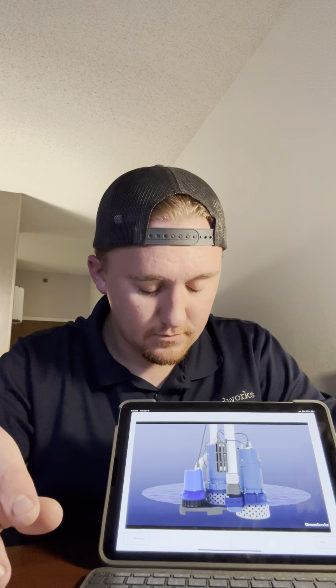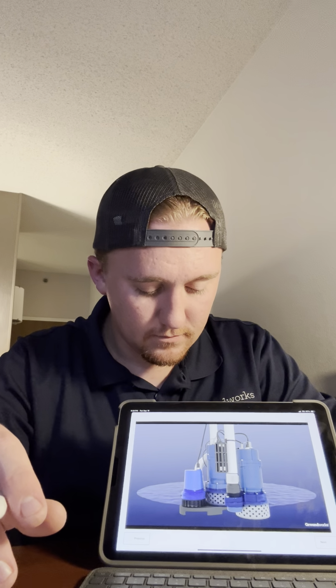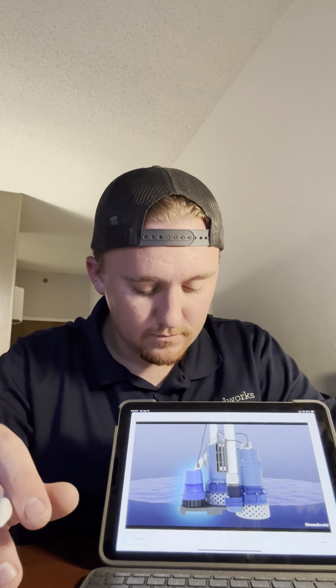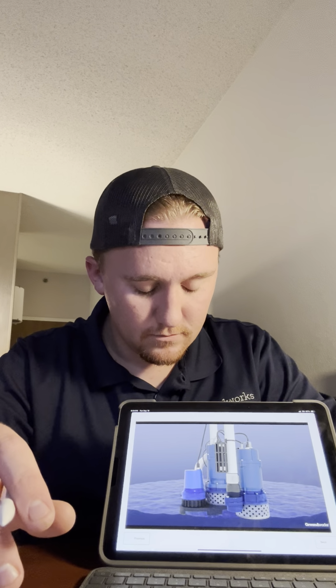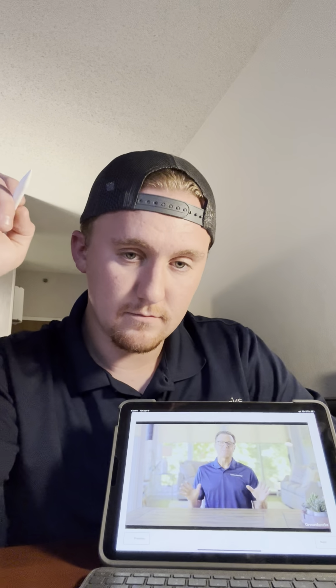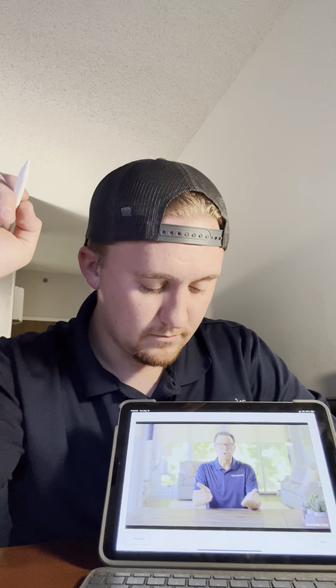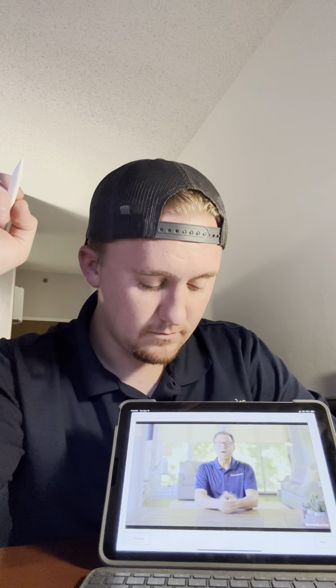If power is lost and the water rises above the level of both these pumps, a third sump pump, which is connected to a battery backup, now takes over. In the unlikely event that water passes all 3 operating ranges, the AquaStop monitoring system alerts you to rising water, allowing you to take preventive action.